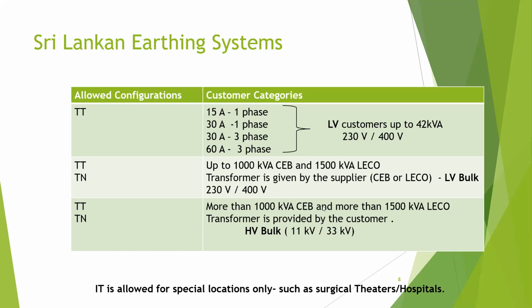And if your demand is higher than 1000 kVA for CEB or 1500 kVA for LECO, you are considered an HV bulk customer. For HV bulk, usually the metering is done at the 11 kV or 33 kV supply, because the transformer is provided by the customer. So you have to buy a transformer if your demand is higher than this value. The CEB will connect the meter on the high voltage side of the transformer. Those customers can also have TT or TN.